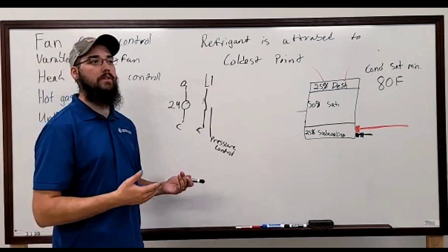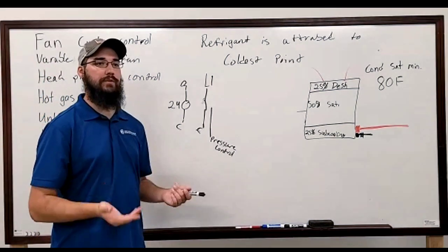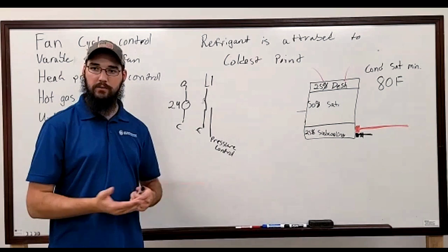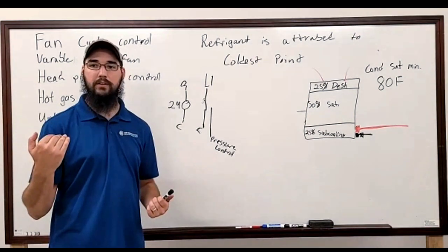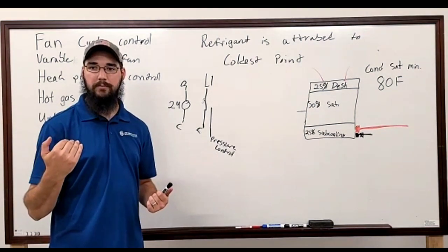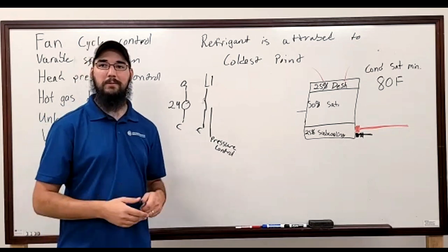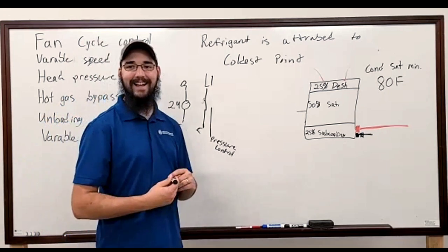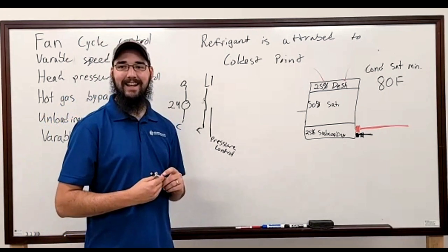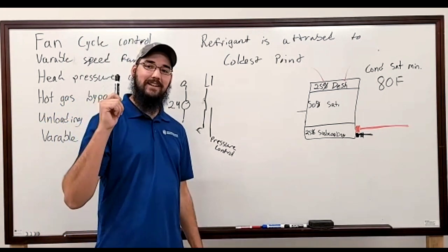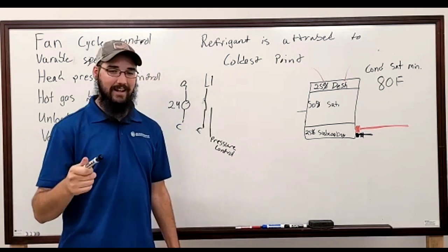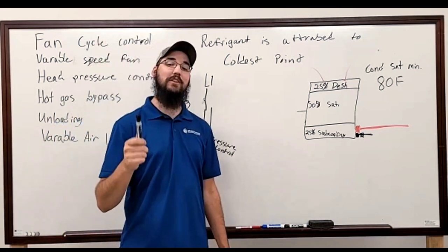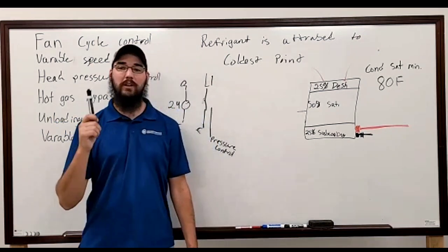Now, we have the defrost control board controlling the fan in heating, because when it goes into defrost, it kills the fan. Well, we'll have a heat pump class coming up. We just talked about how we didn't want to kill the fan to keep it from freezing. Right. Now we're talking about heat pumps, now we're talking killing the fan. Yes. That is where we'll get into.